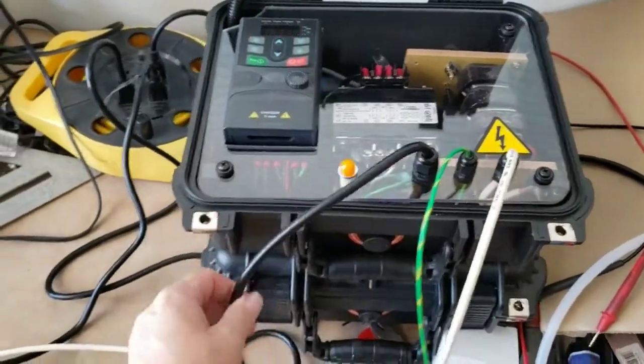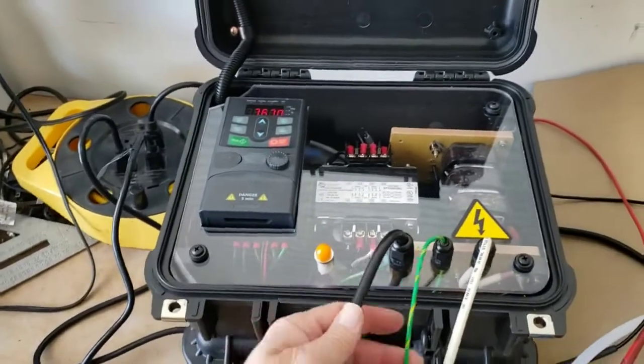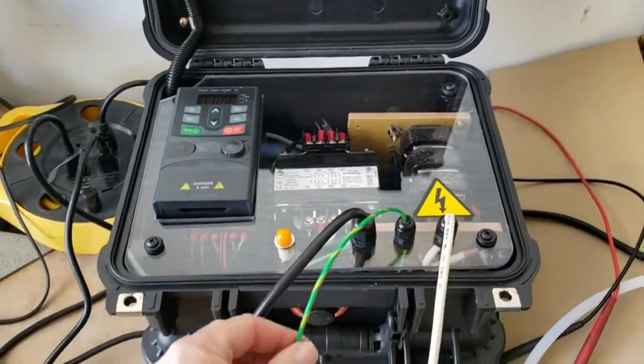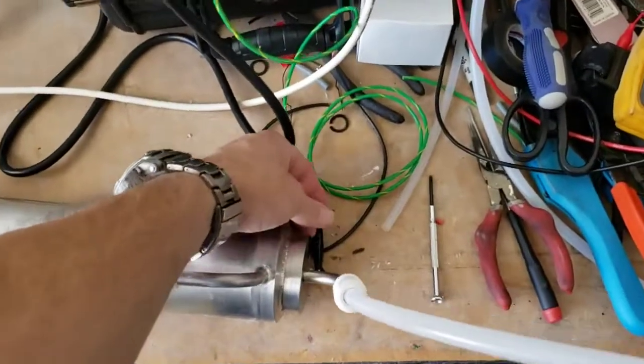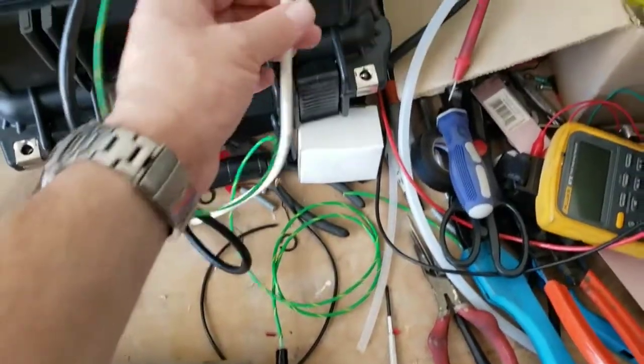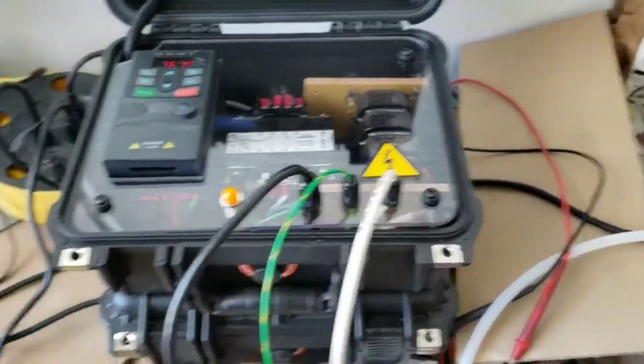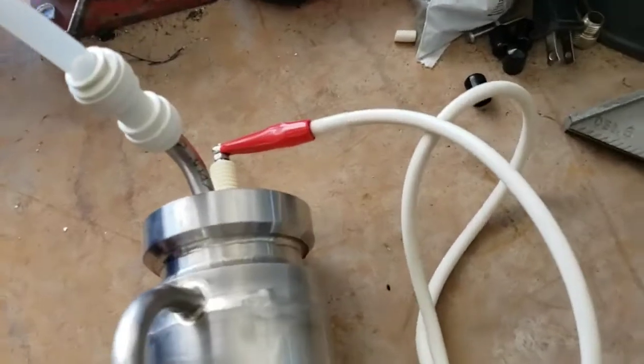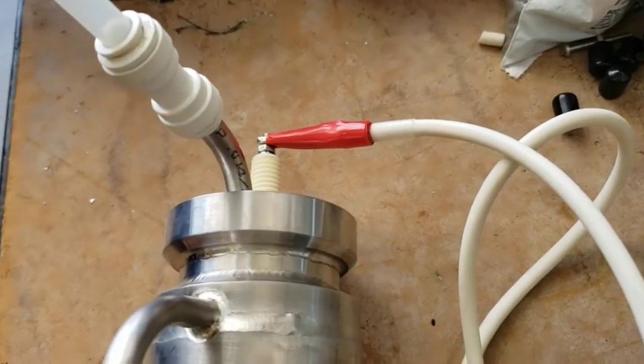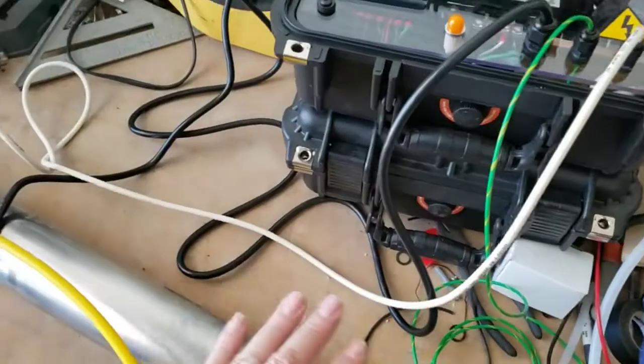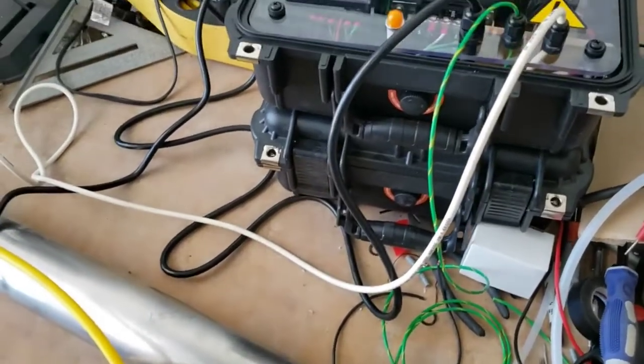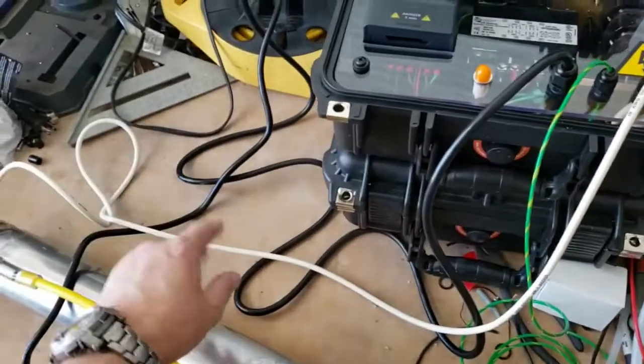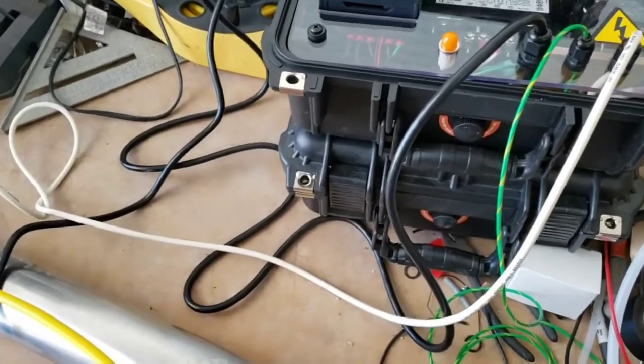You've got a 110 volt plug to plug it in and power it. You've got a ground lead that clamps onto the cell. And then of course you've got your high voltage lead that clamps onto the high voltage bushing or probe on the cell. Keep clear of the high voltage wiring while you're doing any tests, and try to keep it clear of any metal on the chassis.